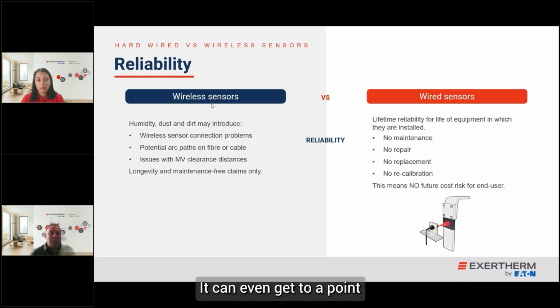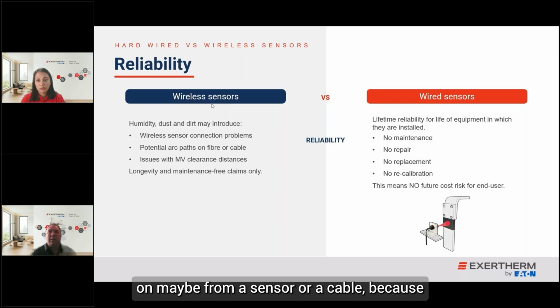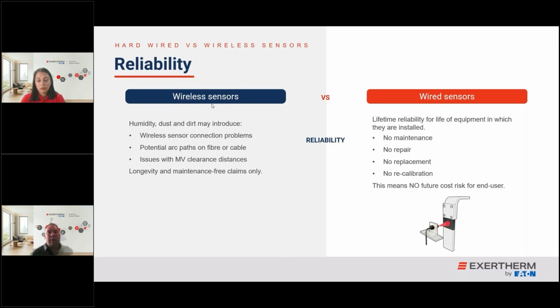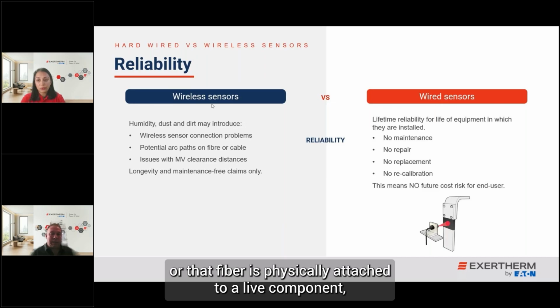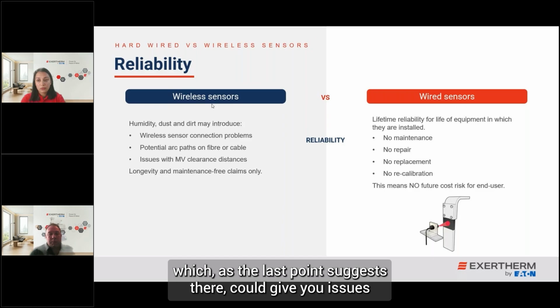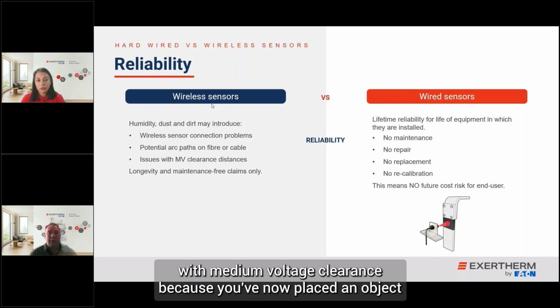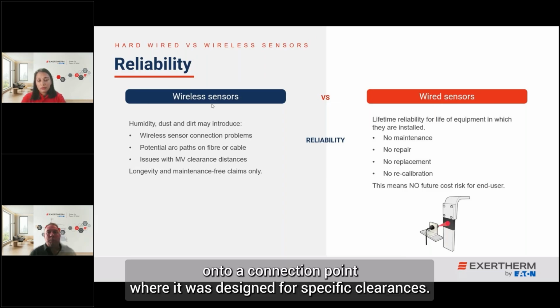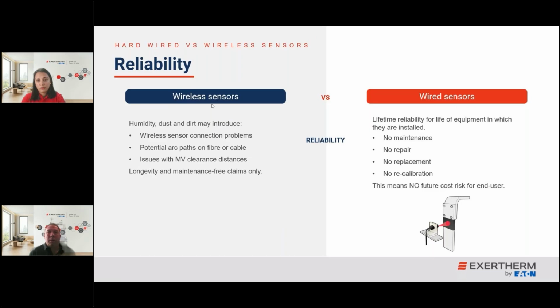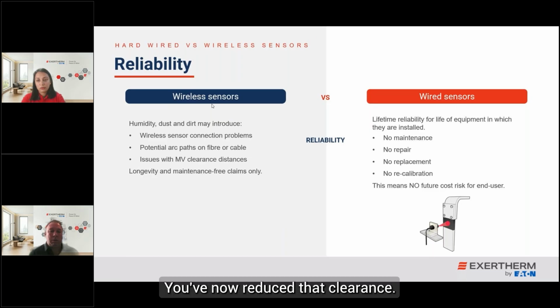It can even get to the point of creating an arc path from a sensor or cable, because that wireless sensor or fiber is physically attached to a live component. As the last point suggests, this could cause issues with medium voltage clearance, because you've now placed an object onto a connection point that was designed for specific clearances, and you've reduced that clearance.